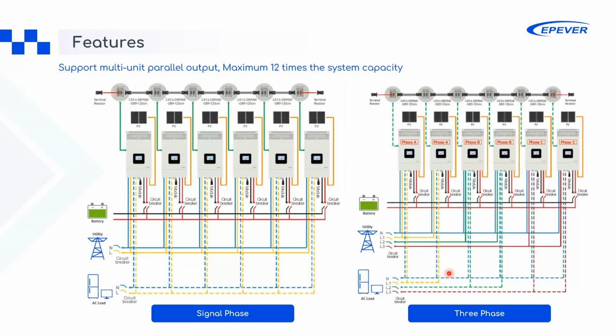The grounding is very important. We need to ensure that all equipment is grounded according to the local electrical codes in your country. We need to carefully manage wiring to prevent cross connections and phase imbalances. Normally we use color-coded wires to maintain clear documentation of the system. Of course, synchronization is also important, being taken care of by the DSPs of the inverters.